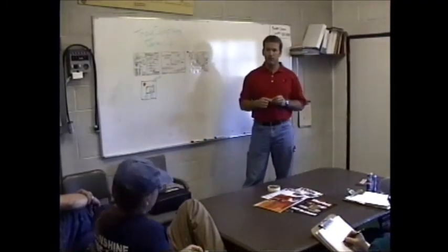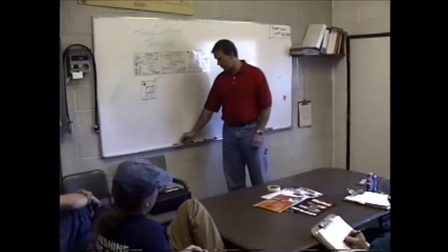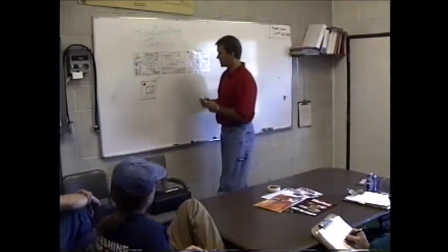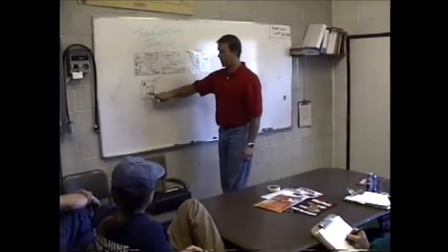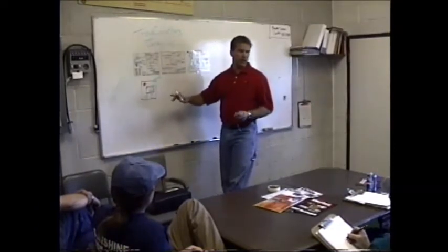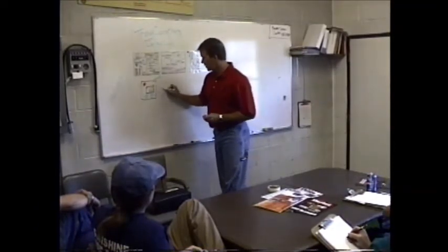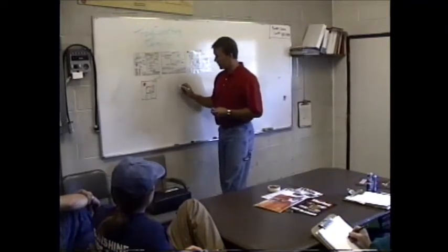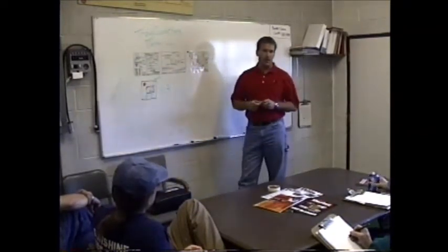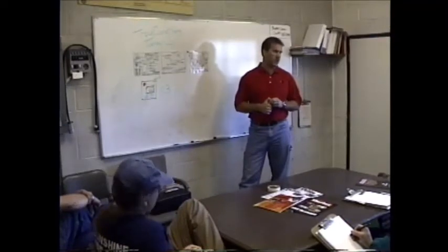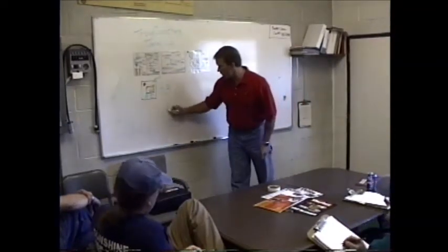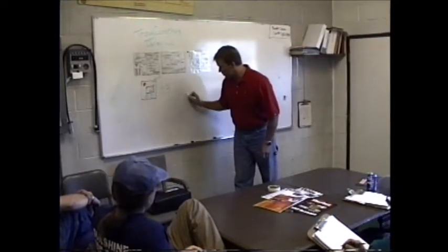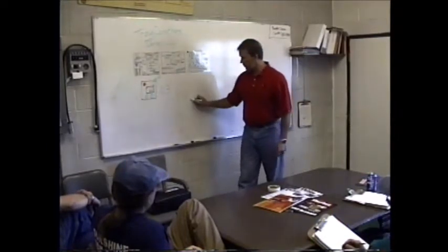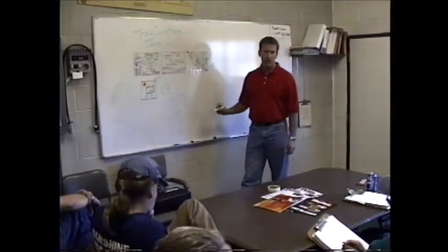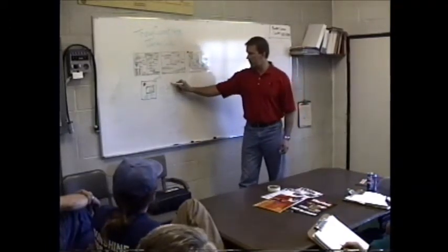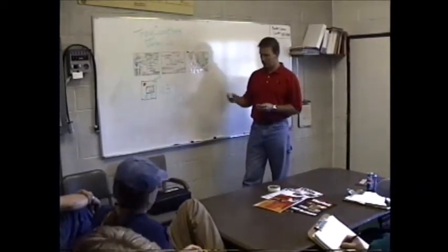The standard for compressed air foam is going to be 0.3%. Okay, so that standard setting, if you push either of these up or down buttons just once, that's a quick way to check to see what your setting is at. And it'll come up and it'll probably tell you 0.3%. That computes out to for every 1,000 gallons of water you use, you're going to use 3 gallons of foam. Okay? So that's what 0.3% is going to mean to you in actual numbers.